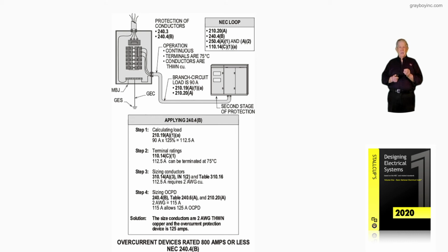If it was 100 amps or less, you could use 100 amp or less type overcurrent device. Now, just the opposite, some engineers and inspectors say, no, step 1 is just a 90 amp load. So based upon the connected load, not the calculated load, we would allow the number 2 to be used.